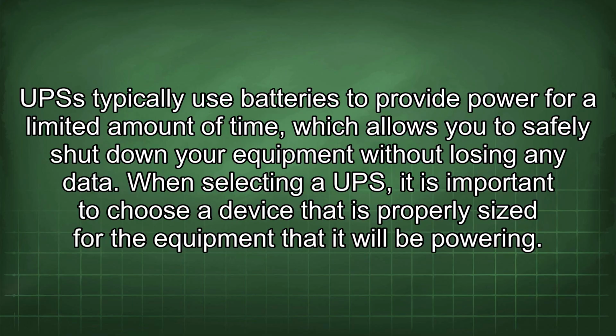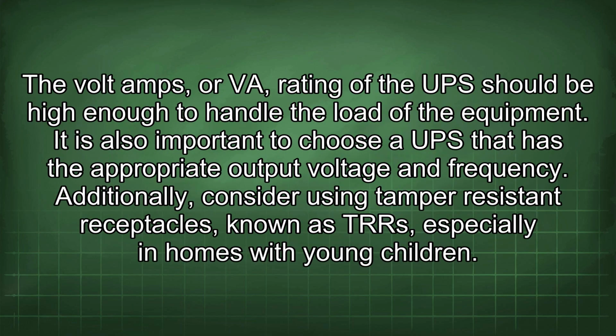When selecting a UPS, it is important to choose a device that is properly sized for the equipment that it will be powering. The volt amps, or VA, rating of the UPS should be high enough to handle the load of the equipment. It is also important to choose a UPS that has the appropriate output voltage and frequency.